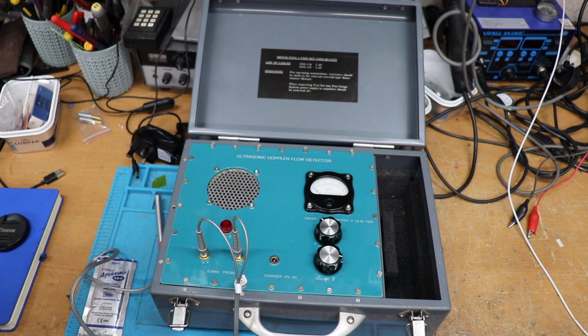And the other thing that you use these machines for, which is the more common use, is for measuring the pressure in the circulation of the blood vessels of the legs. What you would normally do is put a blood pressure cuff around the ankle, and then using this Doppler machine you would detect the Doppler signals over, say, the ankle pulses, and then by pumping up the blood pressure cuff and seeing when the signals disappear and reappear, you can determine the perfusion pressure in the foot.